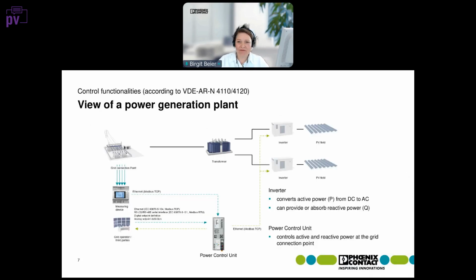Now we have a look at the control functionalities. First, I want to have a look at a power generation plant. This is a very simple power generation plant with 2 PV fields, 2 inverters, the transformer, and the grid connection point. The inverters convert active power from DC to AC and can provide or absorb reactive power. And the power control unit, here in the bottom middle position, controls active and reactive power at the grid connection point. And here you can see all the interfaces.